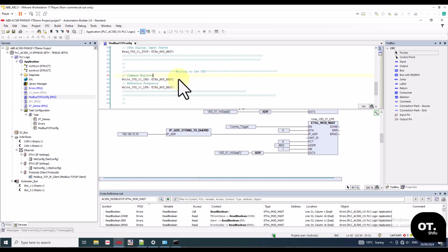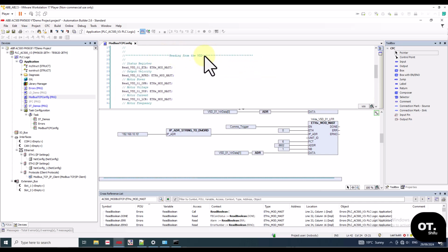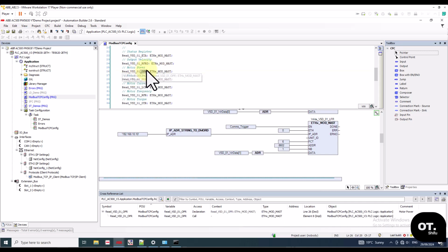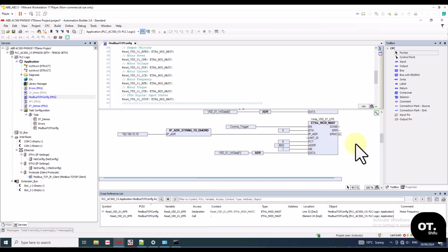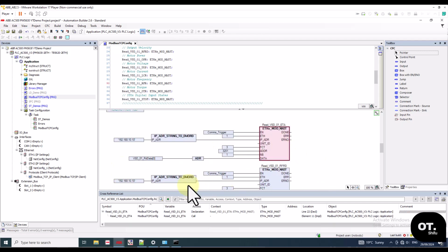And we're going to read those registers: motor voltage, motor power, motor current, motor frequency, motor torque. We are going to read all of that from the VSD. For each of those registers that we're going to read, we have a function block, and we have the address as we got it from SOMOVE, the logical address of the particular function.